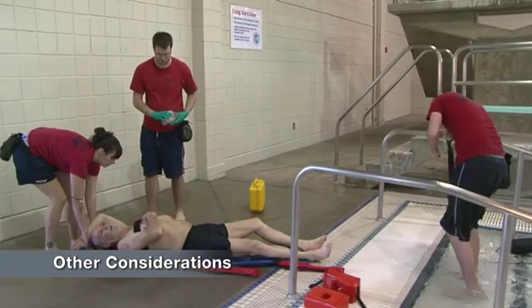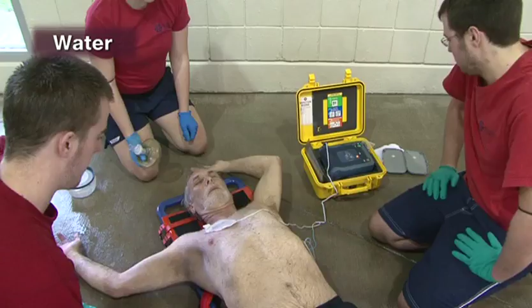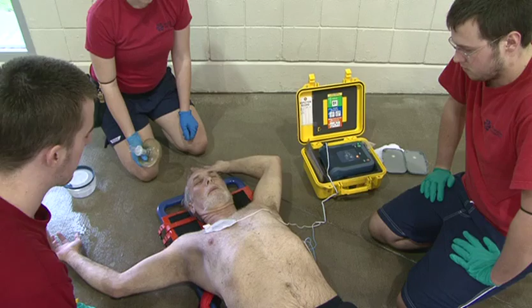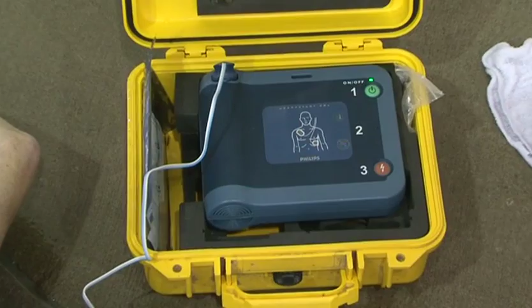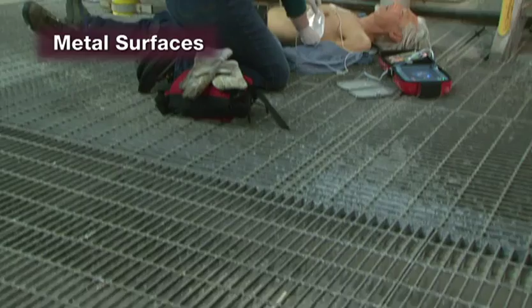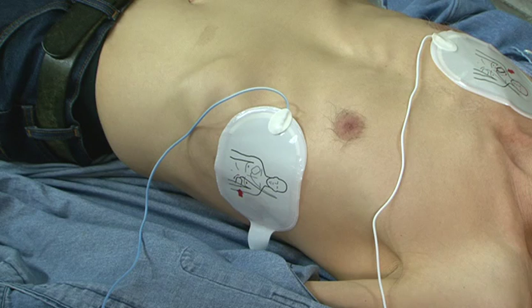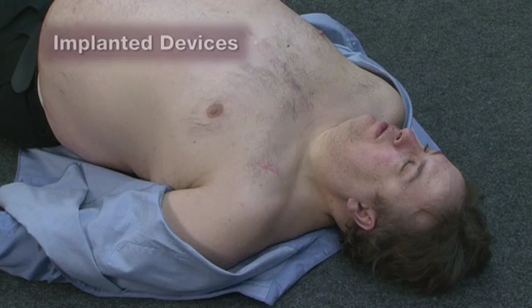A person should be removed from standing water before using an AED. It is okay to use an AED when a person is lying on a wet surface, such as in the rain or near a swimming pool. An AED should never be immersed in water or have fluids spilled on it. AEDs can also be used safely on metal surfaces, such as gratings or stairwells. Make sure pads do not directly touch any metal surface.